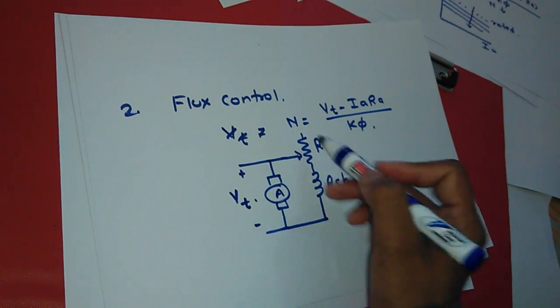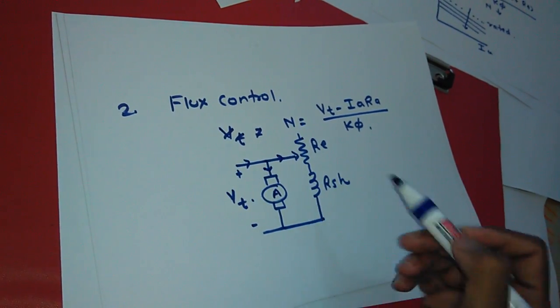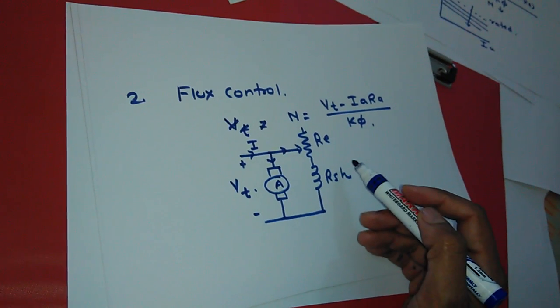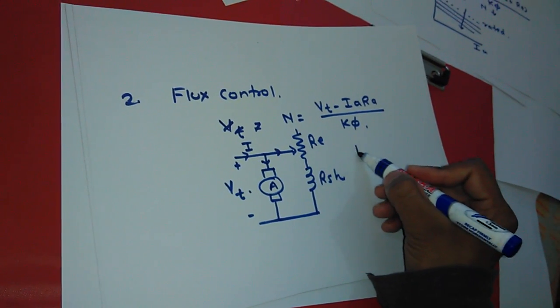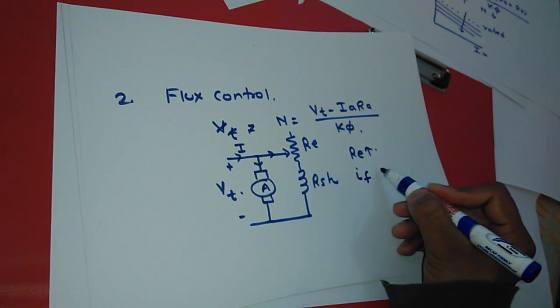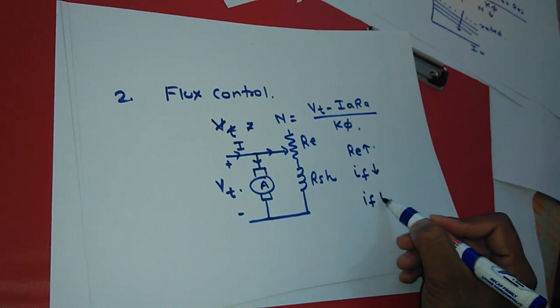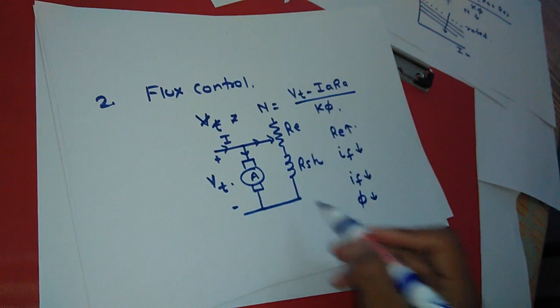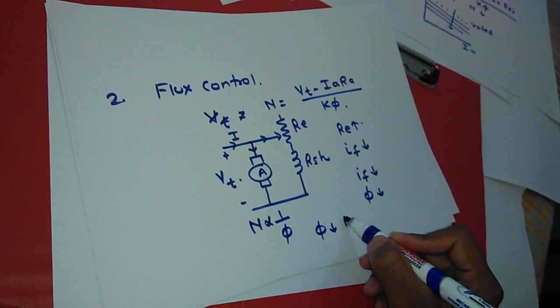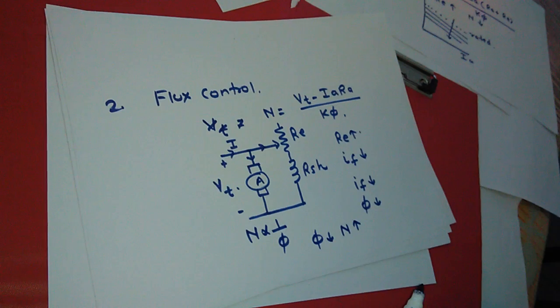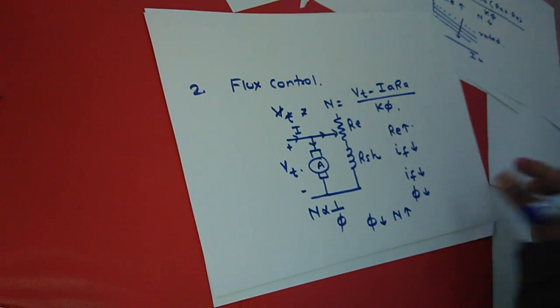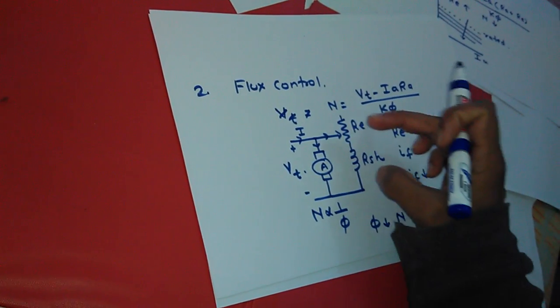In a shunt motor, by changing the resistance of the field circuit we can decrease or increase the current. As we increase the external resistance Re in the circuit, the current in the field winding will decrease. As If decreases, flux also decreases, and from this relation we can see N is inversely proportional to φ. So as φ decreases, speed will increase, and from this method we can get speed above the rated speed. It is called constant power control because the armature part is constant and only the field part is changed.